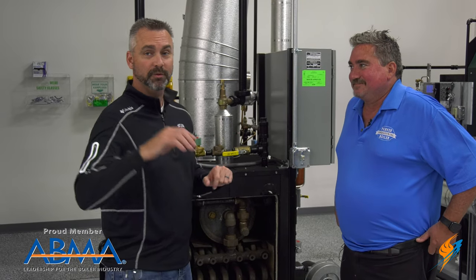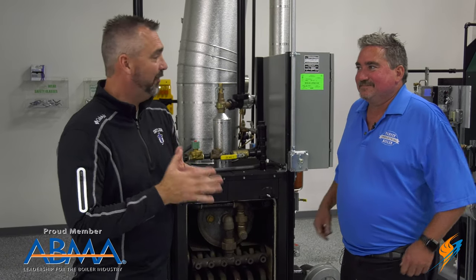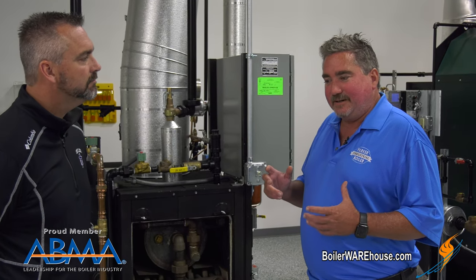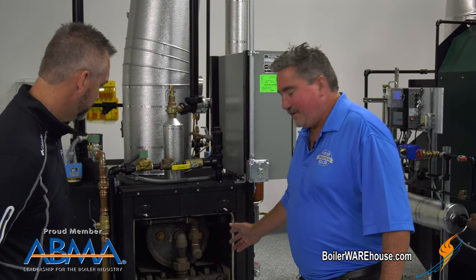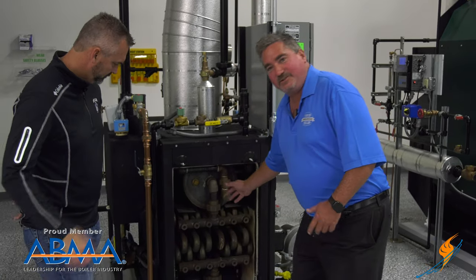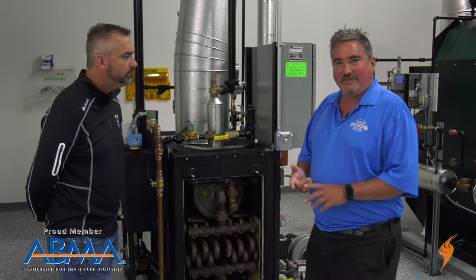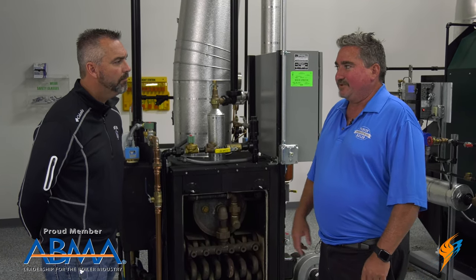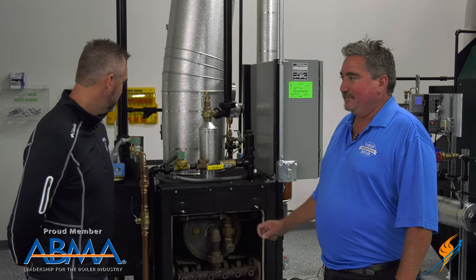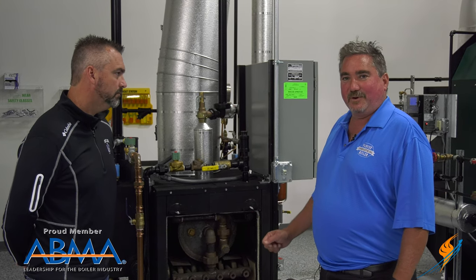It's always good to let people know what all of these are used for — we want to recognize Parker Boiler but also educate on how this boiler is used. The one thing we always brag about is it's the last boiler you have to buy because it's a modular design. There are no welded parts you have to remove as the pressure vessel. If you had to replace the tubes because you were careless with water treatment, you just disconnect the unions and the tubes slide out — put in a brand new bundle. You don't have to have an R-stamp or any certification in most states to do the repair. Same with the drum.